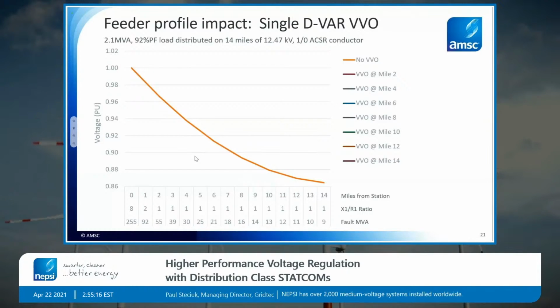And what now we're going to show is how does a STATCOM impact this voltage profile? So not just one point of voltage, but the total profile of the feeder as we put it at different locations on that feeder. So here's the first graph of that, where we're putting a STATCOM 2 miles from that substation. And now we're going to keep moving that STATCOM 2 miles, another 2 miles out each time. So now we're 4 miles from the substation, 6, 8, 10. And what we can see is that the further out the STATCOM goes, the more impact it's able to have on the voltage. And so that's what I described previously, where the downline locations on a feeder are where the STATCOM is most effective, which is good because the downline locations on a feeder are the ones that are often most challenged by these power quality issues. So let's just finish this out, and we see that now at the very end, we're in fact impacting voltage by about 8%.